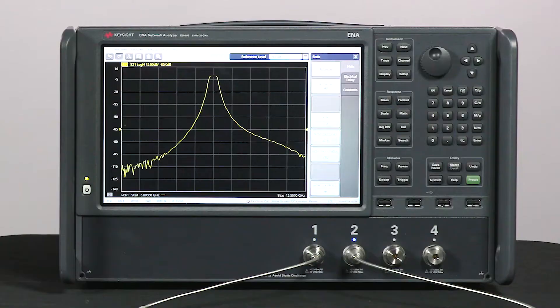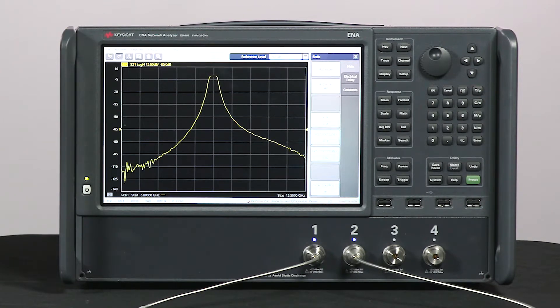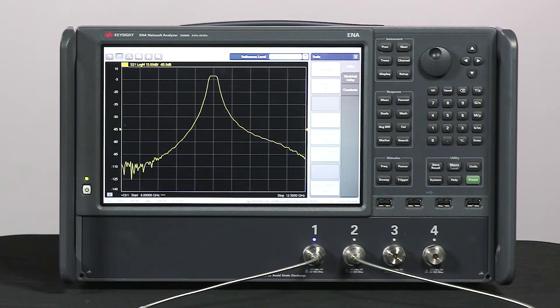Now we can see the noise floor is at about minus 95 dB. This is much better than the E5071C's noise floor at minus 85 dB when we did this same test, thanks to the upgraded hardware in the E5080B.